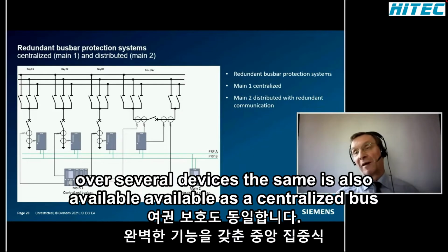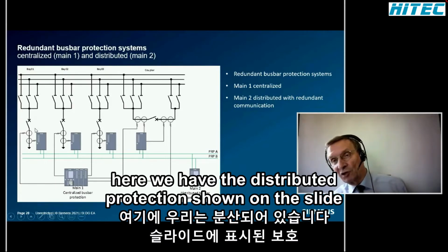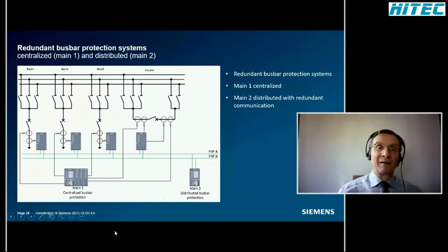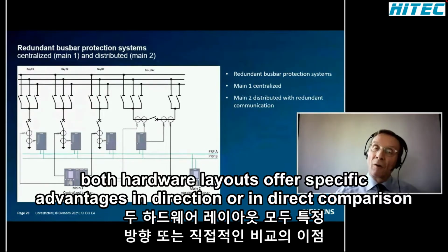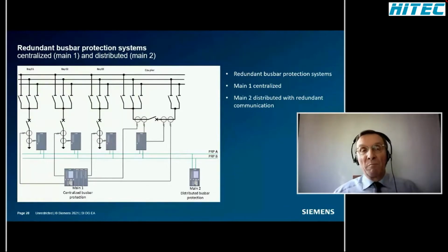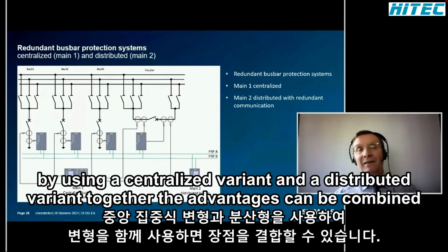SIPROTEC 7SS85 is available as a distributed busbar protection with functionality shared over several devices. The same is also available as a centralized busbar protection with a complete functionality in only one device. Here we have the centralized, here we have the distributed protection shown on the slide. Both hardware layouts offer specific advantages in direct comparison. By using a centralized variant and a distributed variant together, the advantages can be combined in a main 1, main 2 solution.